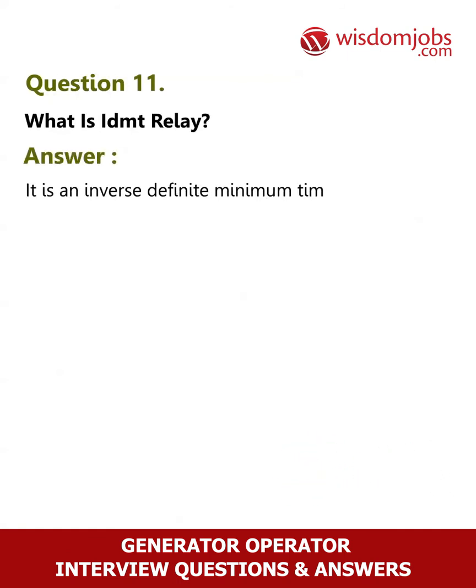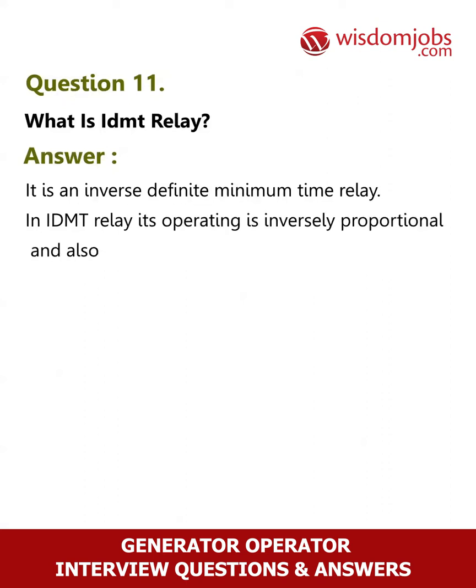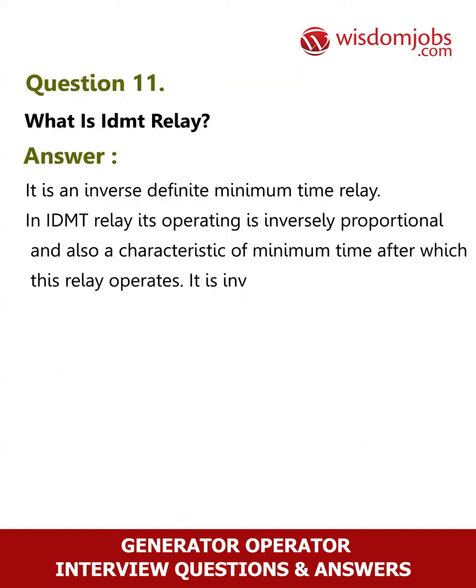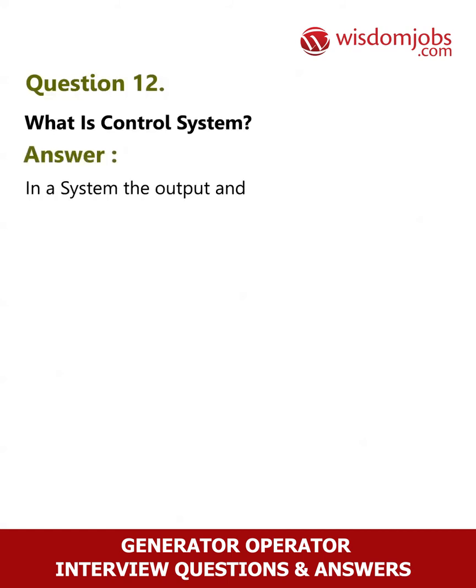Question 11: What is an IDMT relay? Answer: It is an Inverse Definite Minimum Time relay. In an IDMT relay, its operating time is inversely proportional and there is also a characteristic minimum time after which the relay operates. It is inverse in the sense that the tripping time will decrease as the magnitude of fault current increases.